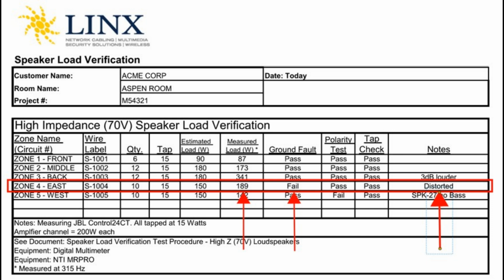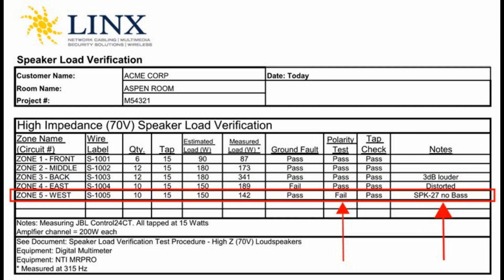The Zone 4 speaker circuit has a ground fault problem and the measured load exceeds the expected load by quite a bit. The note says the audio sounds distorted, which is a common feature of a ground fault problem. The Zone 5 shows a failed polarity test at speaker number 27.